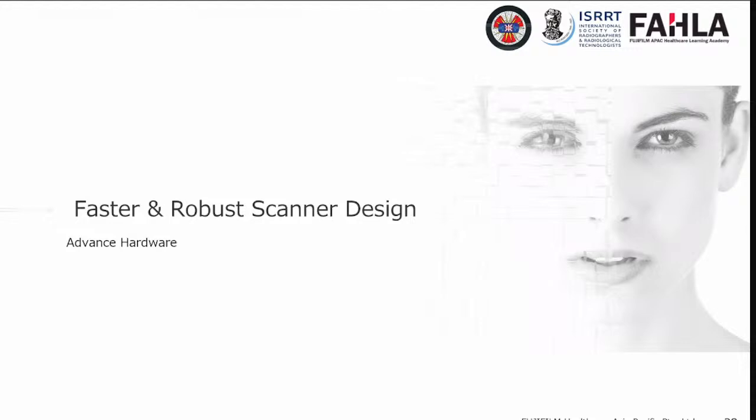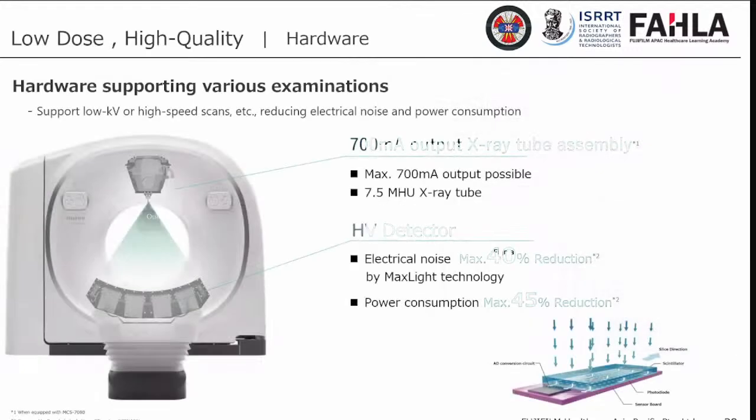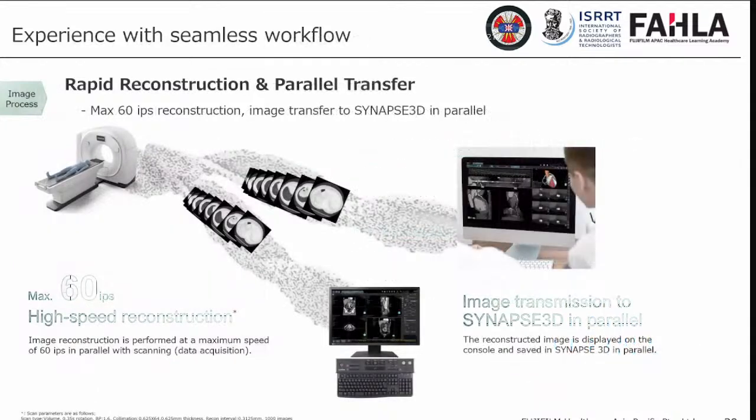But here I would like to say that the existing workhorse scanners have also advanced in terms of a more advanced tube assembly with a more sensitive detector, where we can already start eliminating electrical noise and also manage power consumption, with more powerful reconstructor hardware that is available.